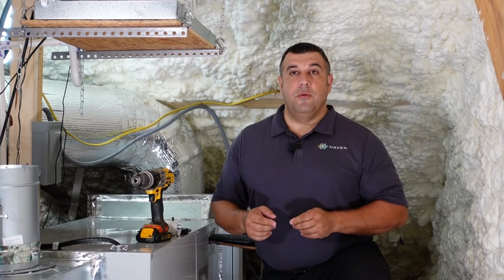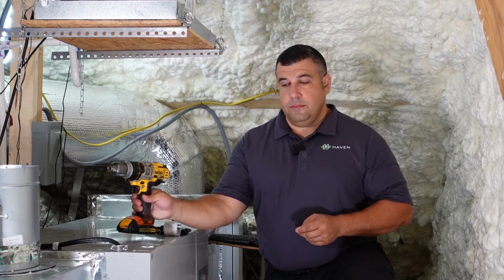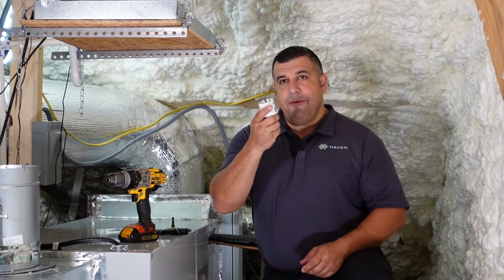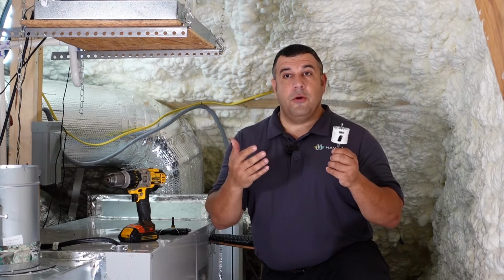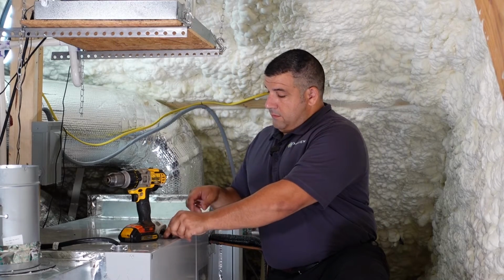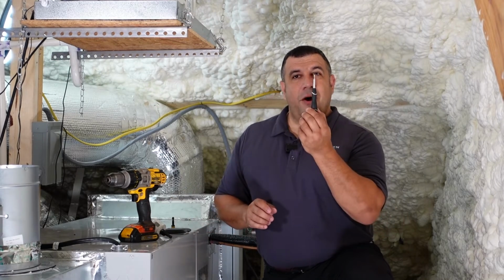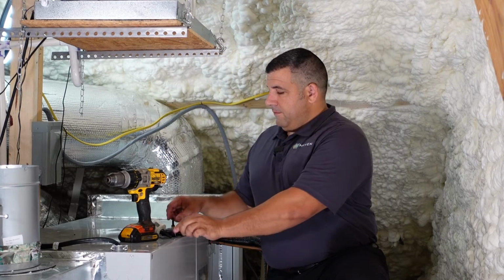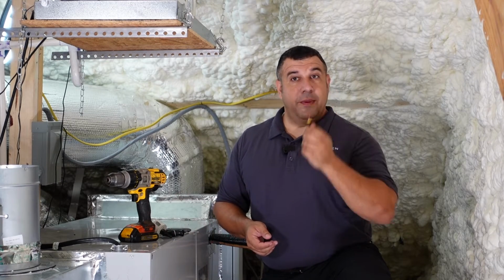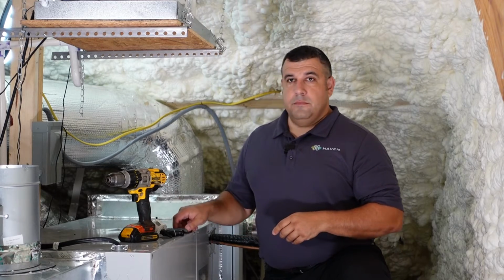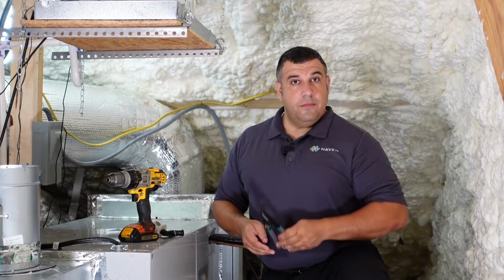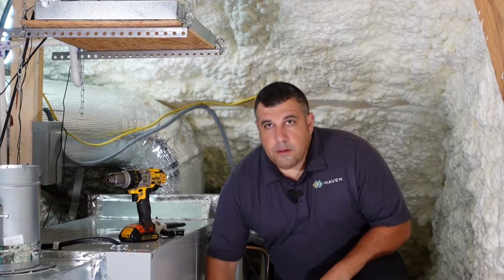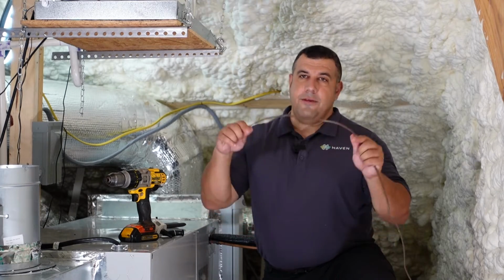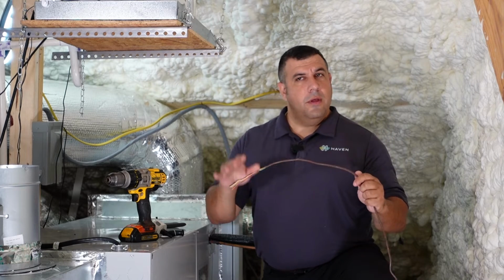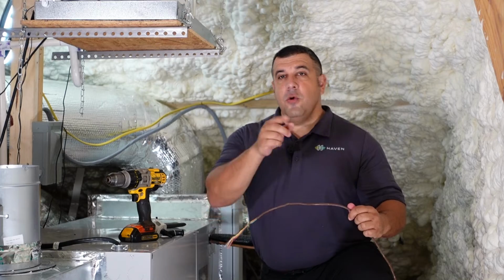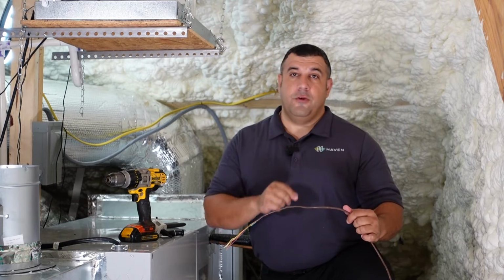You'll need to have the following tools on hand: a drill, a 1.5 inch hole saw for flat ductwork or a 2 inch hole saw for round ductwork, a small slotted screwdriver, a 1/4 inch hex bit, wire strippers, and a length of 2 wire solid conductor cable, but any thermostat wire will work. For the newer version of the mounting plate, you'll only need the 2 inch hole saw.